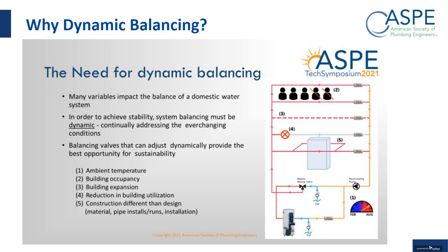The other thing is building occupancy. When we came out of COVID and people started coming back to buildings to work, we started seeing or hearing of issues where they weren't getting hot water. And the reason being because the system was never balanced. When the occupancy was at 100%, there was lots of activity with the lavatories and things like that.